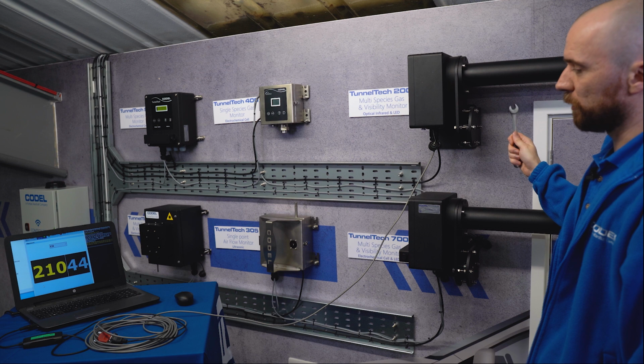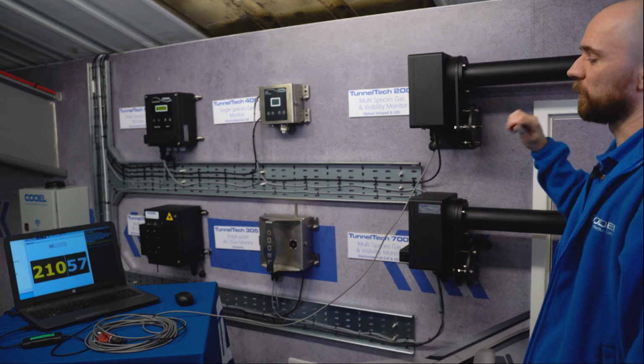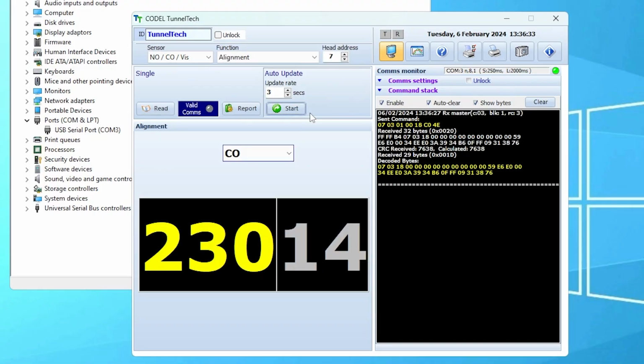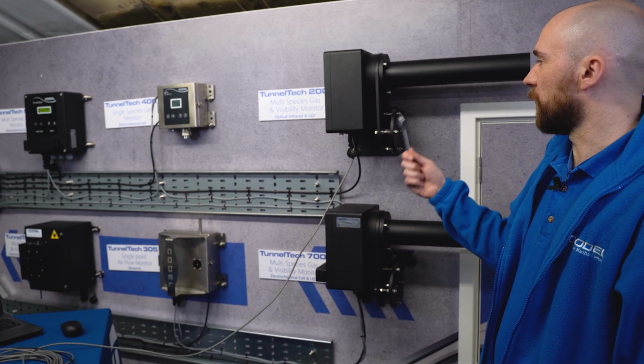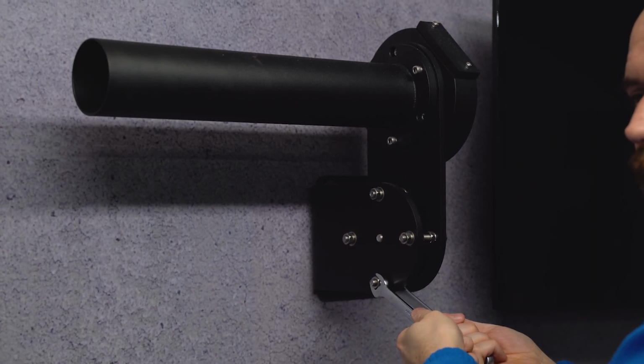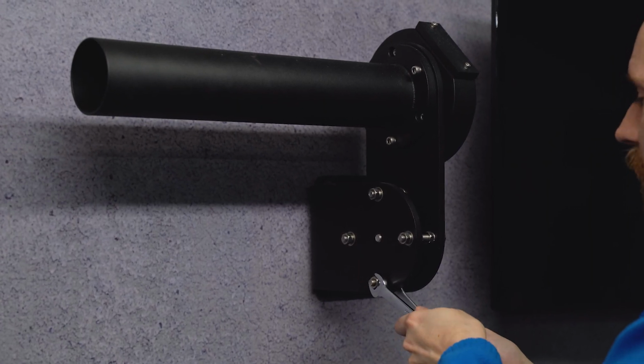We repeat this process going one plane at a time. So we go vertical, then horizontal, then vertical, then horizontal. The aim of the process is to maximize the number we see on the screen. So we're not aiming for any particular detector level. We're just making inputs on the alignment process until we maximize the number displayed on the screen. Once you've maximized the head end, then you repeat the process at the mirror end.